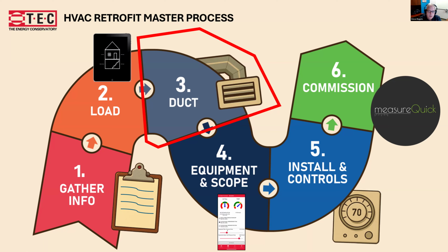But before we get to that, I hope it's not a surprise to anybody that to get the best performance out of a retrofit HVAC system, you need to be gathering information about the existing system, and gathering information from the occupants about how the previous system was working or not working. Step 2 would be a load calculation. I hope that's not a surprise to anybody. This can be done in 20 minutes now with the modern LiDAR scanning load calc tools. And then we do the duct evaluation, step 3.